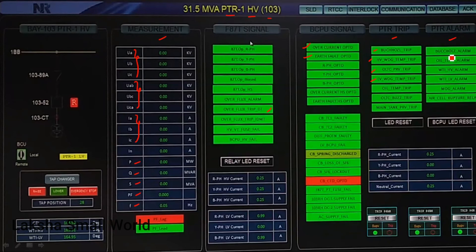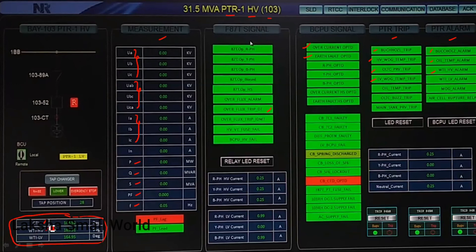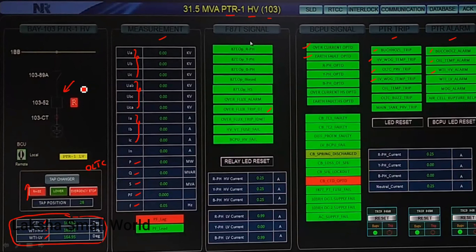This section shows PTR alarms — for minor problems inside the transformer such as Buchholz relay alarm, oil temperature alarm, and winding temperature alarms. At the bottom you can find the temperatures: oil winding temperature, HV winding temperature, and LV winding temperature. From here you can also raise the tap position of the OLTC (onload tap changer) by clicking on the tap changer control. And by clicking on the circuit breaker parameter, you can trip the circuit breaker directly while sitting in the control room. These are the main advantages of automation.